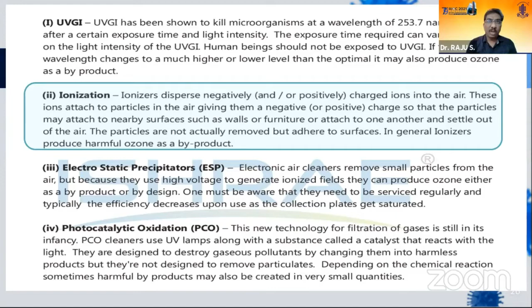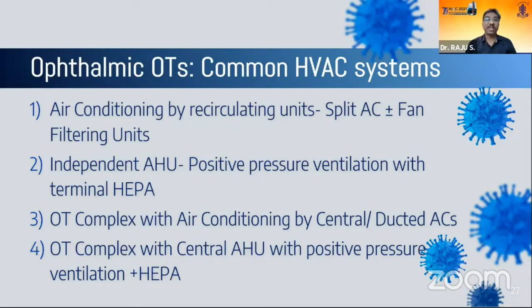Coming to the OT, the most common HVAC systems that we commonly use in ophthalmic setups are the split ACs. They are recirculating units. Fan units can also be added in these OTs. The next commonly used system is the independent air handling units, which are positive pressure ventilation systems with a terminal HEPA. Very big hospitals have an OT complex with central air conditioning which is supplied through ducts, or you may have an OT complex with a central AHU with positive pressure ventilation and HEPA. So these are the various systems that are available for all of us.